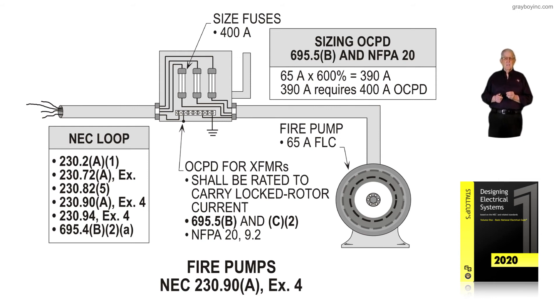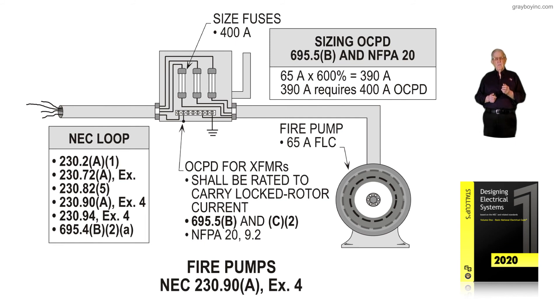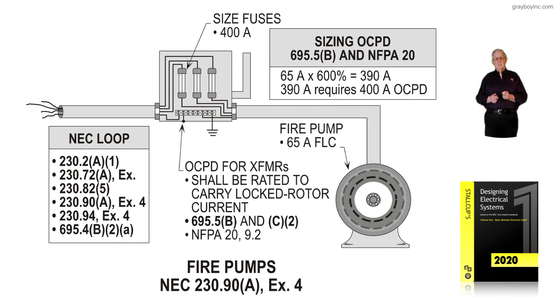Some states, counties, and cities prohibit a tap ahead of the main, so you really need to check that out. 230.90 exception number 4 allows sizing that overcurrent device to allow a fire pump to operate and bring water to a location until failure. 230.94 exception 4 further deals with this permissive rule for fire pumps. And 695.4B2A also states the overcurrent device must be sized to allow the fire pump to operate till failure.